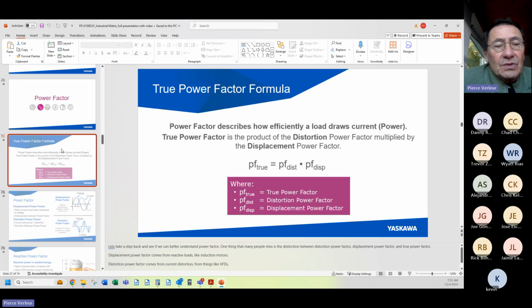97% of the energy is being used to move the water to its destination. Put a gate valve in there, or turn 90 degrees, or neck the pipe down, and the power factor goes down because you're wasting more energy going around the 90-degree curve, or the turbulence caused by the gate valve. But in a direct connection, it's very efficient.